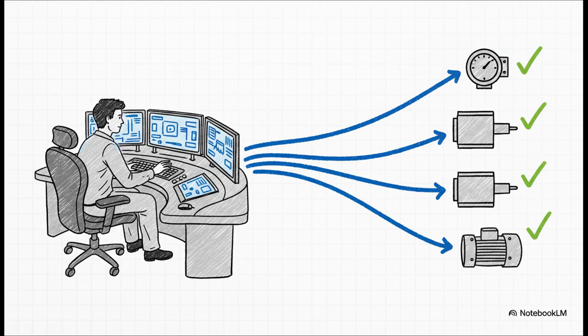Next up is commissioning, the part where you actually get the plant fired up and running. With PROFIBUS, one single technician sitting comfortably in a control room can set up and test over 100 devices in a single day. Think about that. Gone are the days of needing a whole team running around the plant, checking every single instrument one by one.